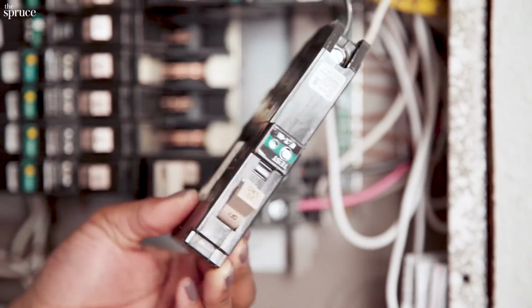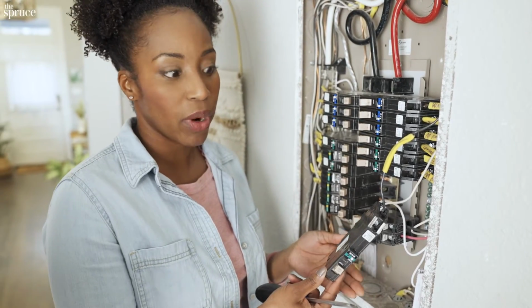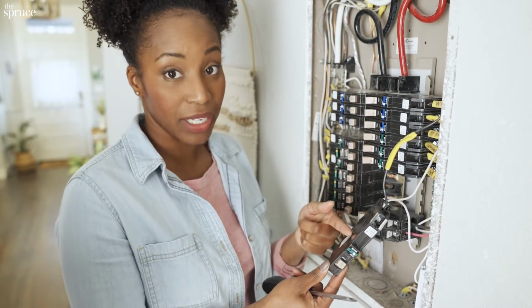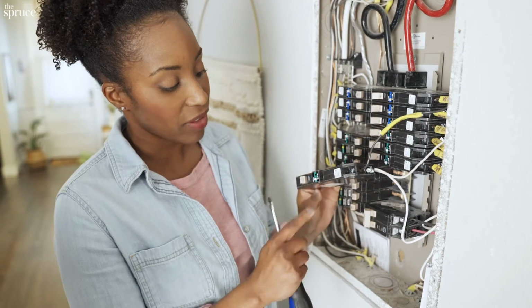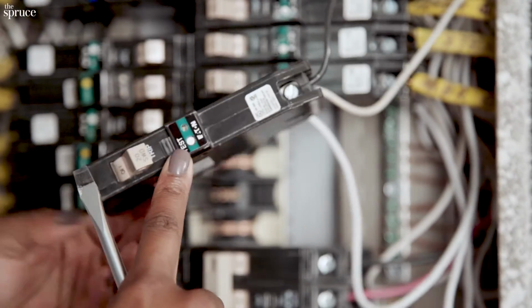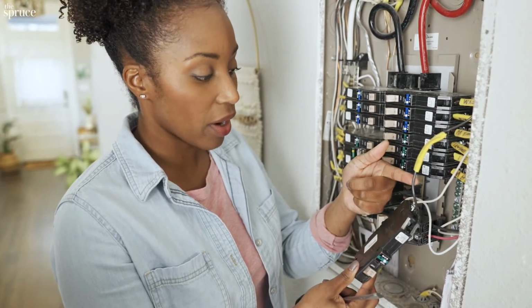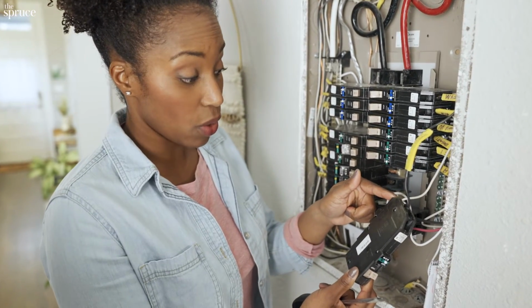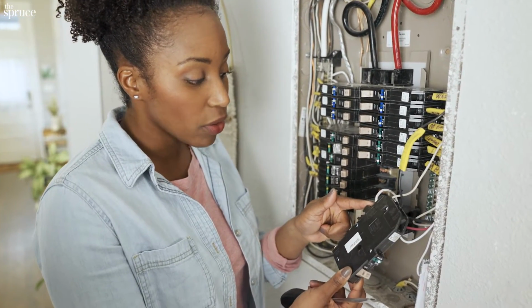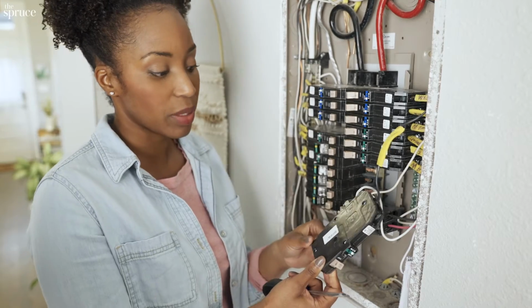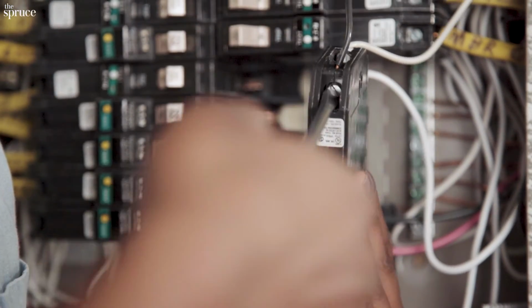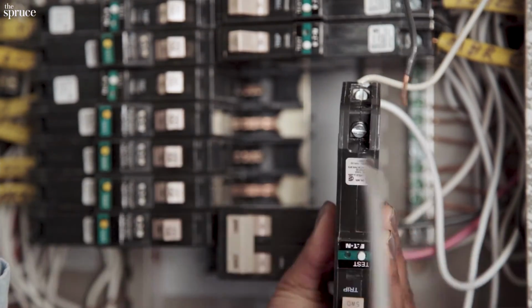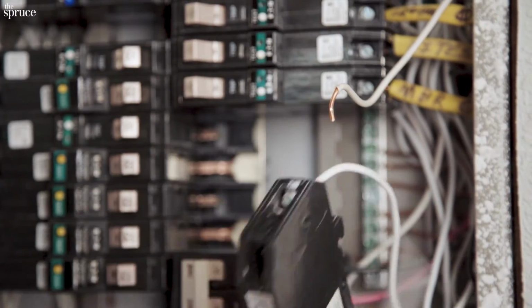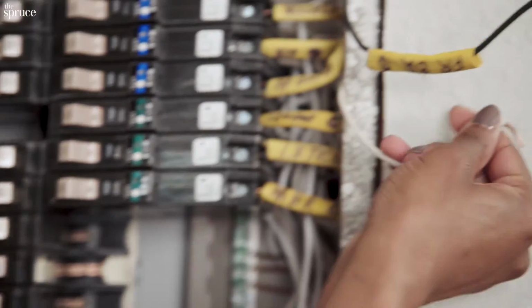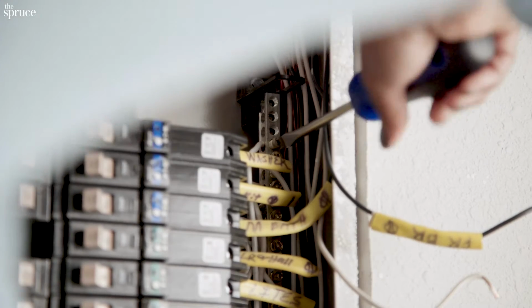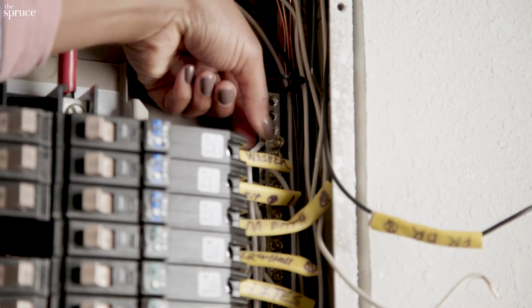Now it's time to remove it. A standard single pole breaker will have one hot wire attached to the terminal. If you have a GFCI or AFCI breaker, you'll have a hot wire and a neutral wire, as well as another neutral wire that connects to the neutral bus bar. To remove them, you'll loosen up the screws. Perfect. And this last one, I'll have to loosen right here at the bus bar.